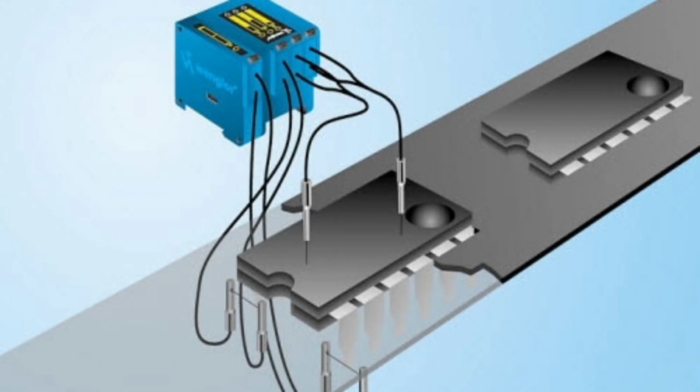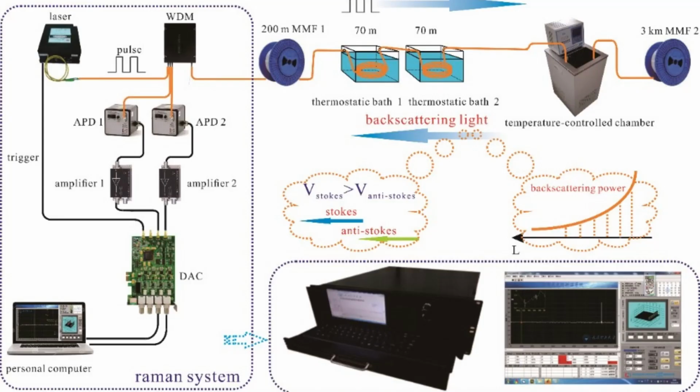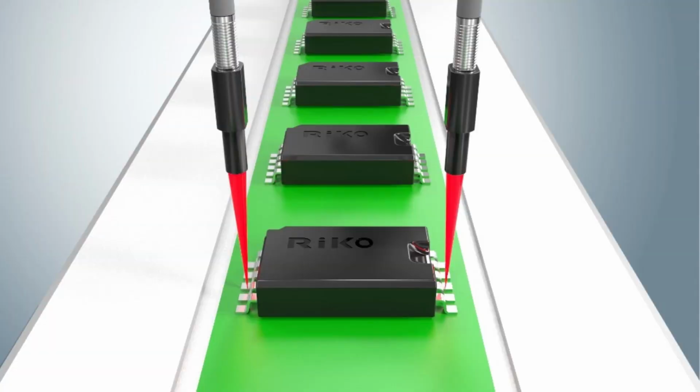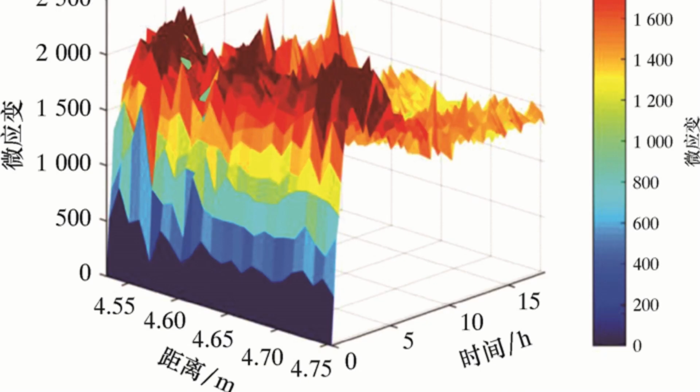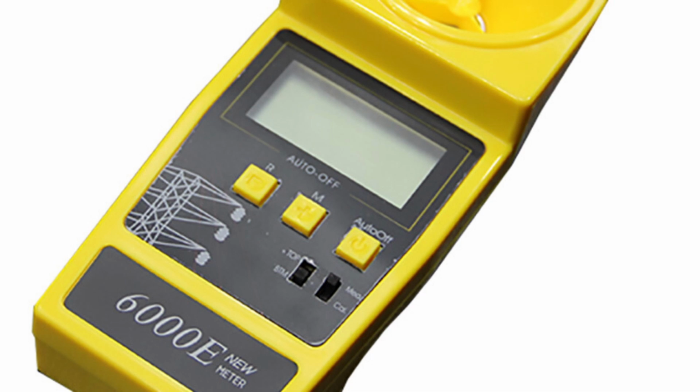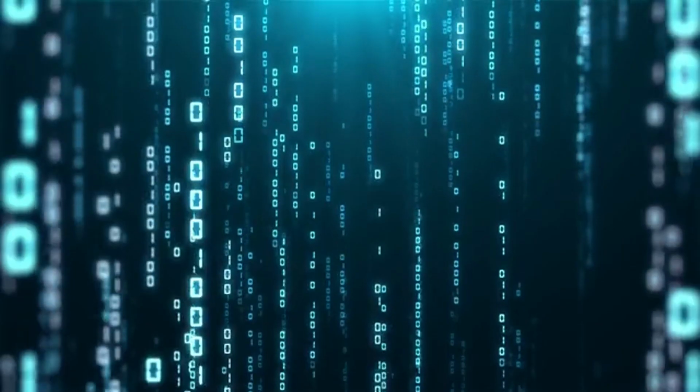A fiber optic cable can act as the communication path between a test station and an external sensor, which is known as extrinsic sensing. However, when the fiber itself acts as the fiber optic sensing system, this is known as intrinsic fiber sensing. The benefit of this type of fiber sensing technology is that discrete interfaces between the fiber and external sensors are not required, which reduces complexity and cost. In order to make this possible, external stimulation such as temperature and strain fluctuations need to influence the light source within the cable in a measurable way to provide useful data.